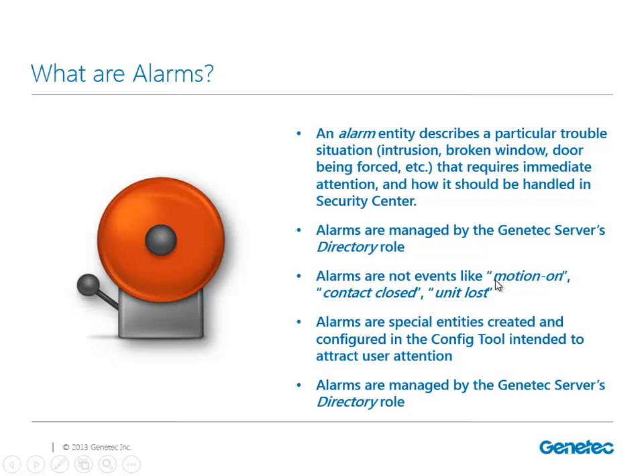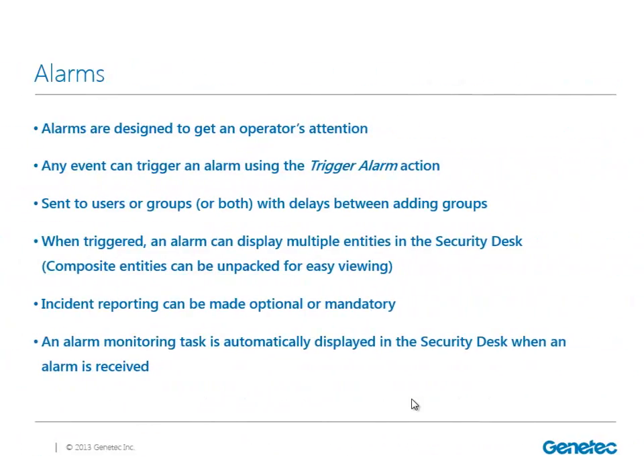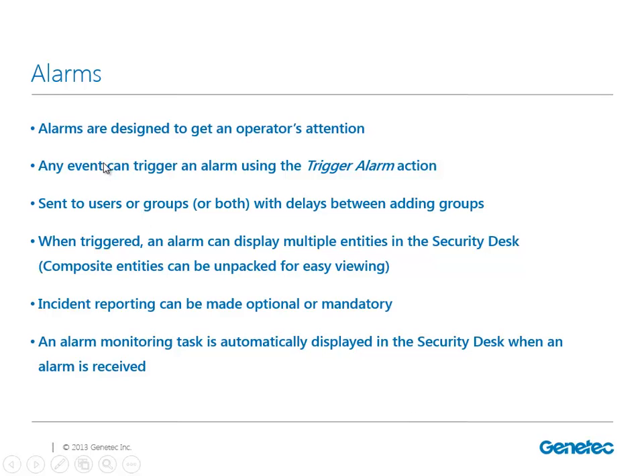In our case, it will be an operator or whoever is in front of our Security Desk application. The alarms are being managed by the directory role. Alarms are designed to get the operator's attention. It's very important to understand that we must be a recipient of the alarm to be able to get that alarm in Security Desk. If you're not a recipient — when we create alarms, we have to add a recipient or a group that we need to send the alarms to. If we're not part of that group, then we're not going to get that alarm.